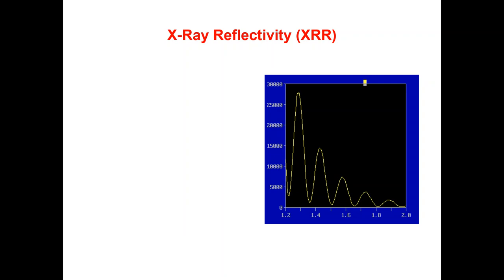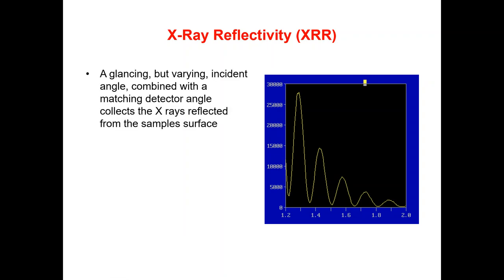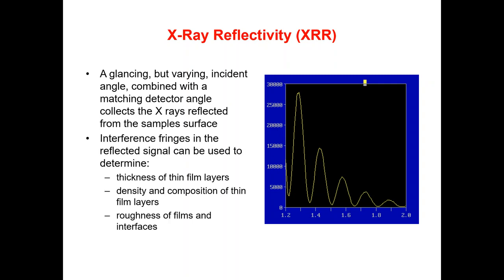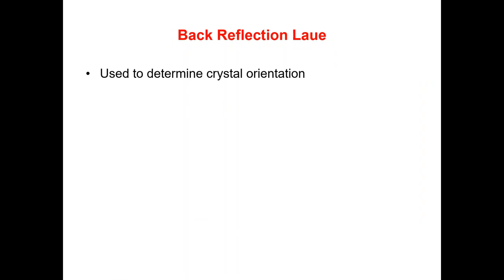X-ray reflectivity, called XRR, uses glancing but varying incidence angles combined with a matching detector angle that collects X-rays reflected from the sample surface. The interference fringes in the reflected signal can be used to determine the thickness of film layers, the density and composition of thin film layers, and the roughness of films and interfaces.